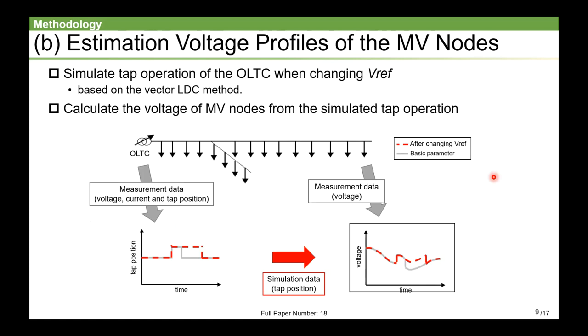Next, I will explain step B in detail. In this step, we first simulate the tap behavior when Vref is changed based on the vector LDC method using measurement data of OLTC. When the simulated tap position is different from the measurement one, like this time, the voltage at MV node is calculated by adding or subtracting the tap width as shown in this figure.